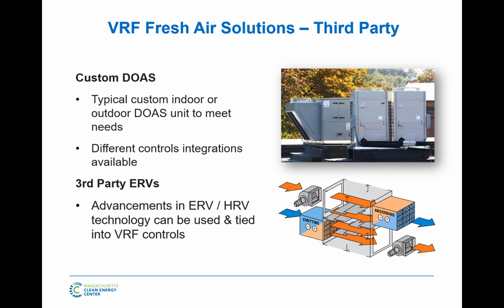I have no chilled water or hot water in the building because I'm doing an all-electric building. But for this part of the building, I need a full 50,000 CFM unit for whatever reason. I need to do some cooling or some heating in it, between wheels or after wheels. We can just put a VRF coil in there. So that's about a lot of the evolution with fresh air.